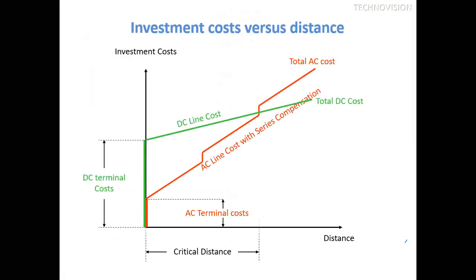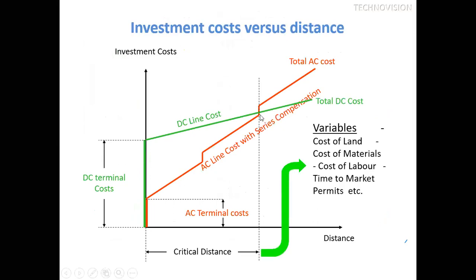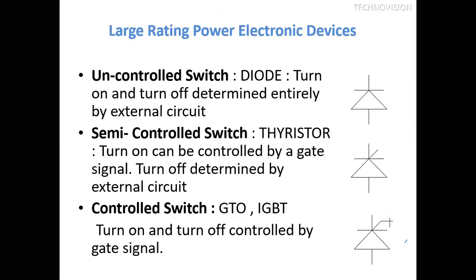Then this is the cost comparison. When the distance increases beyond 700 to 800 kilometers, HVDC is more economical than AC. These are the cost structures. These are some of the devices we use for HVDC transmission. There is the diode, an uncontrolled switch; the thyristor, a semi-controlled switch which we can turn on but cannot turn off; and controlled switches like IGBTs, which we can turn on and off. These are known as force commutated devices, and the others are line commutated devices. Based on these, we have thyristor based technology and voltage source converter based technology.